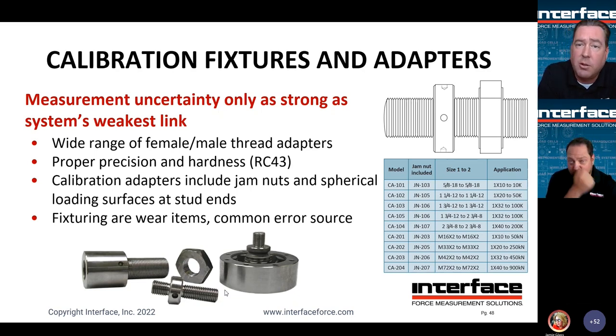You'll notice on this calibration adapter here, we've got a threaded jam nut, and there's a collar feature that can be used with a spanner wrench to locate and then jam down. So that's a precision machined jam nut, and you'll also notice there's a spherical radius on the end of that calibration adapter, and that's if you wanted to use this for a compression only type configuration. As mentioned again, fixturing is a wear item and potentially a very common error source, so it's important to keep an eye on those items. Slide, please.